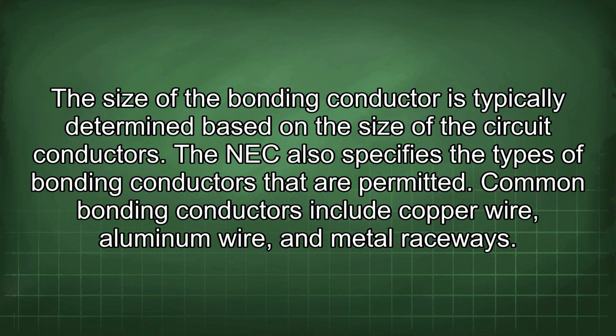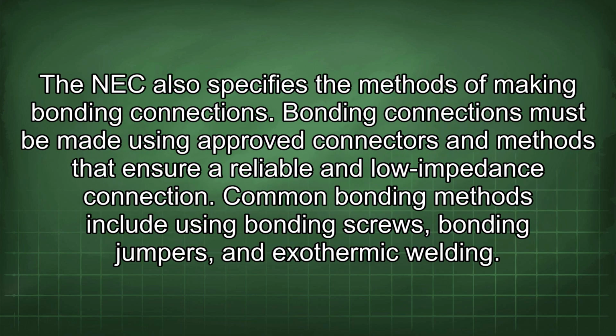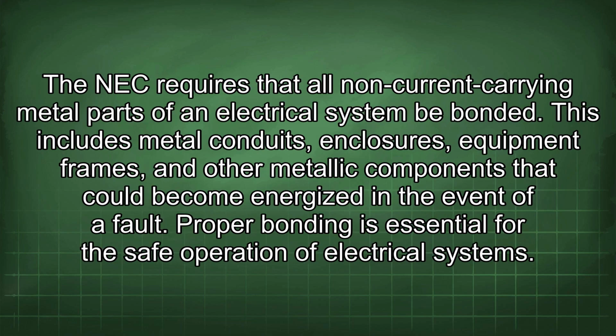Common bonding conductors include copper wire, aluminum wire, and metal raceways. The NEC also specifies the methods of making bonding connections. Bonding connections must be made using approved connectors and methods that ensure a reliable and low impedance connection. Common bonding methods include using bonding screws, bonding jumpers, and exothermic welding. The NEC requires that all non-current carrying metal parts of an electrical system be bonded.